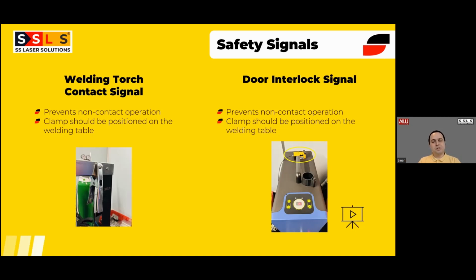So all of our machines come standard with the door interlock signal, and not just the signal - it also comes along with the door switch. So the customer doesn't need to buy the door switch or get the signal interlocked to the door; it is already built in. You may just need to extend the cable if you have a much bigger room than the cable we supplied. That's it. So when the door is open, the machine should be stopping automatically.